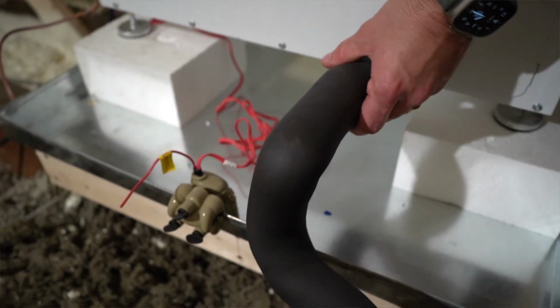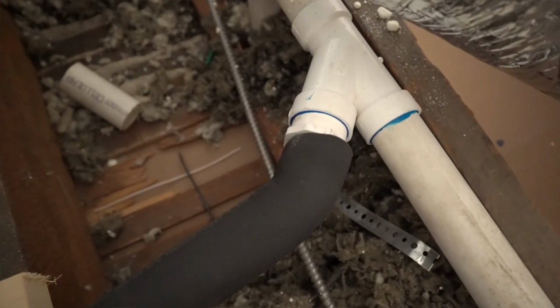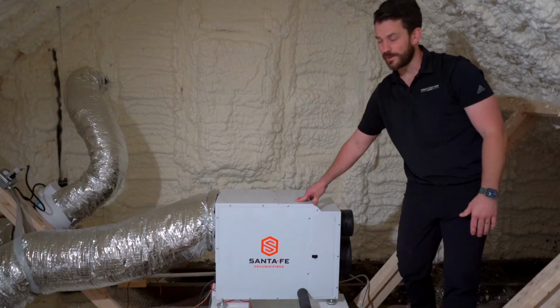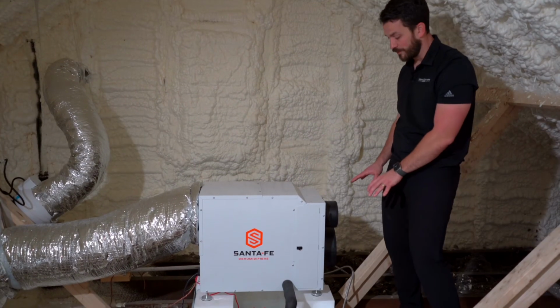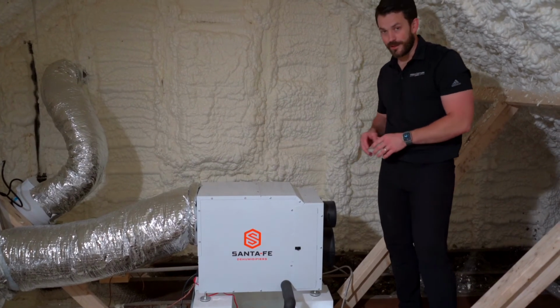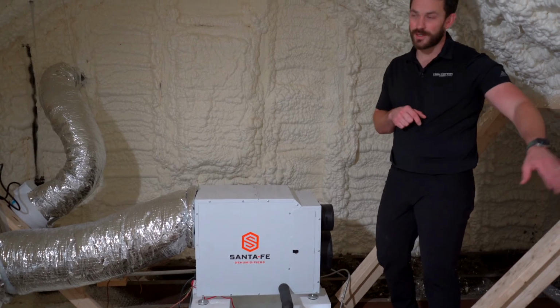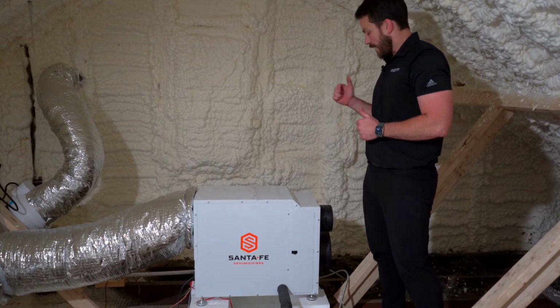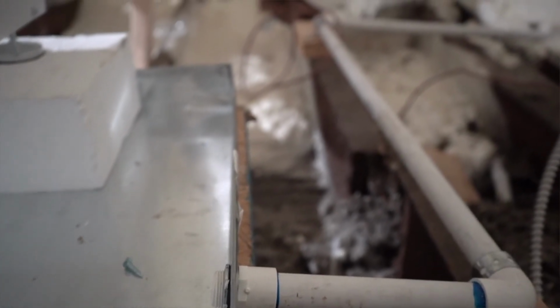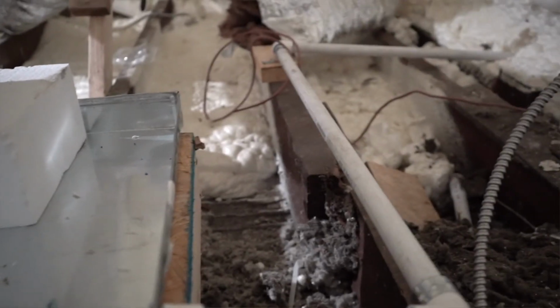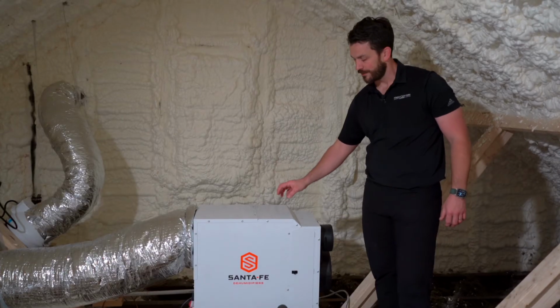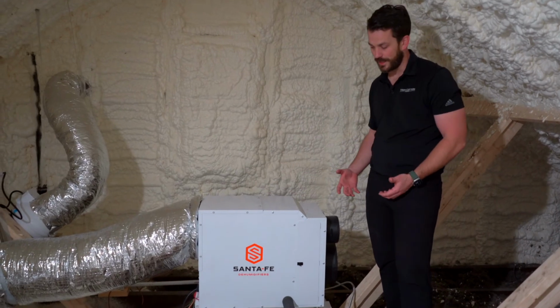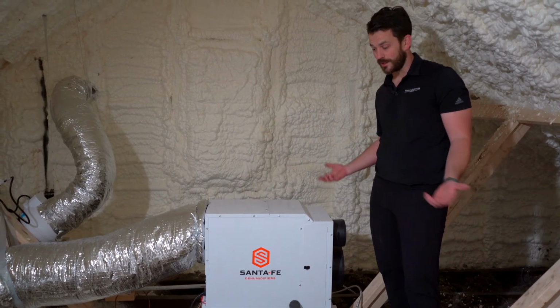This one's wrapped in insulation, but it actually ties into a vent over here, so it drains into the house plumbing, which is nice. We built a little platform so it's elevated, giving enough fall for the condensate to drain by gravity. There's also an overflow drain in the condensate pan that goes out the side of the building as an emergency, in case of a failure where the pan starts to fill up, to protect the ceiling below.